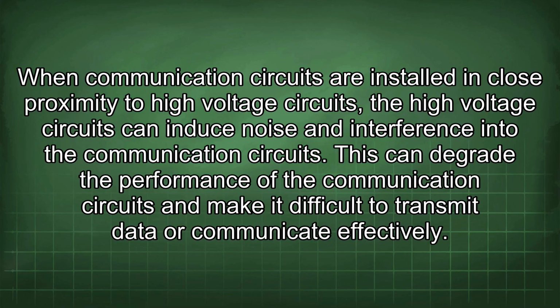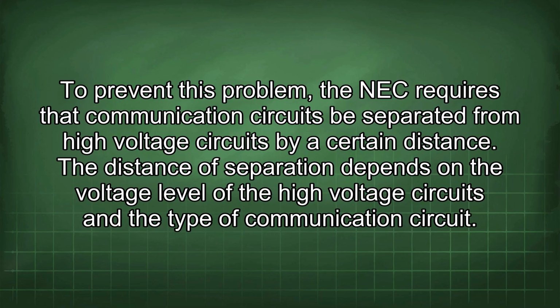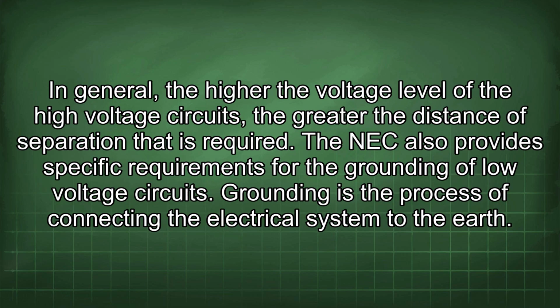communicate effectively. To prevent this problem, the NEC requires that communication circuits be separated from high-voltage circuits by a certain distance. The distance of separation depends on the voltage level of the high-voltage circuits and the type of communication circuit. In general, the higher the voltage level of the high-voltage circuits, the greater the distance of separation that is required.